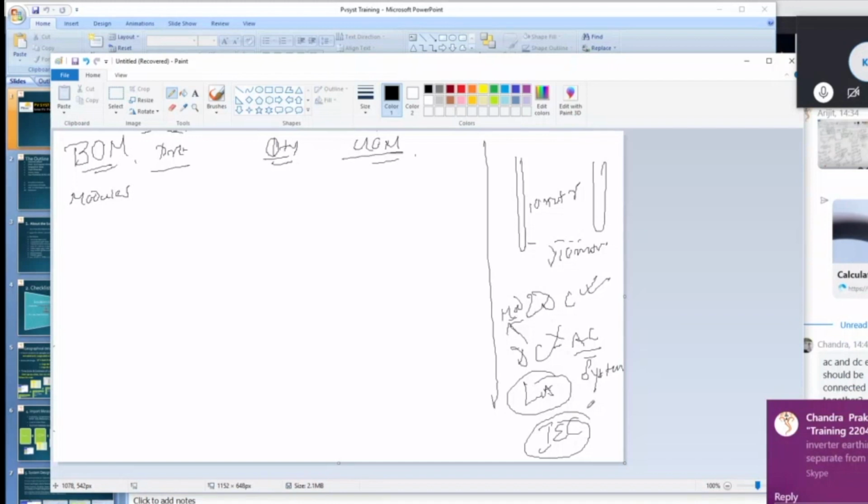Yes, inverter earthing should be different from DC. For AJB and module earthing, the AJB structure will go to the DC earthing. The inverter, being an AC component, will go to the AC earthing. Only in a few inverters where there is no internal SPD present, for example Power One.